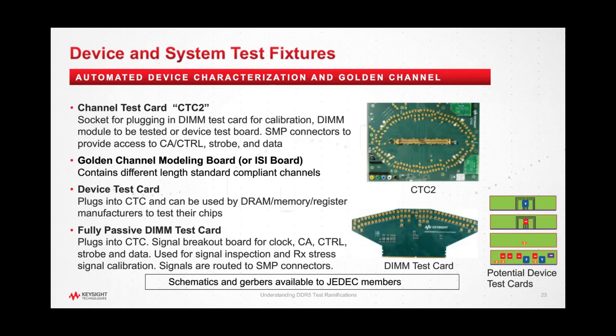Then there is, or will be, a different type of device test cards. These plug into the DIMM socket on the CTC2, and are used to test DIMM, DRAM, RCD, or buffer chip. More detail about the device test cards will be discussed later.